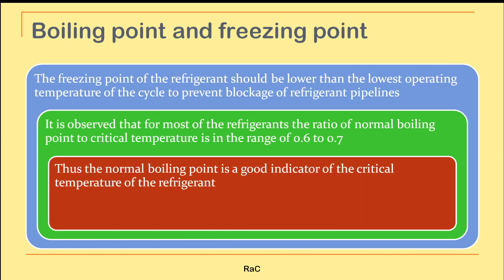The freezing point of the refrigerant should be lower than the lowest operating temperature of the cycle. For example, if the evaporator is meant to maintain minus 10°C, the freezing point of the refrigerant must be below that — otherwise the refrigerant will freeze, blocking the pipeline in the evaporator and stopping flow entirely.